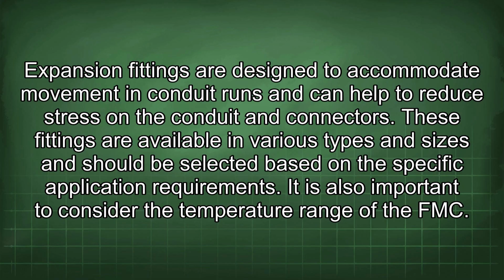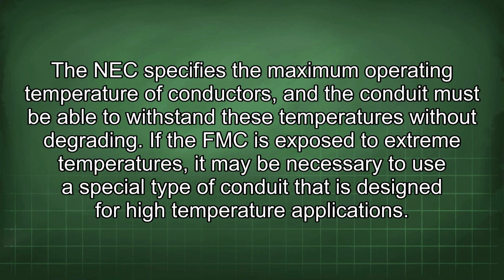It is also important to consider the temperature range of the FMC. The NEC specifies the maximum operating temperature of conductors, and the conduit must be able to withstand these temperatures without degrading. If the FMC is exposed to extreme temperatures, it may be necessary to use a special type of conduit that is designed for high-temperature applications.